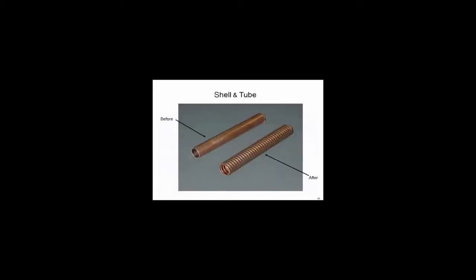Some changes: if you haven't looked at heat exchangers lately, whether they're chillers, evaporators, or single pass counter flow like we're talking about, the old designs were just standard copper tubing. The new designs are enhanced tubes. It's just spiral tubes, very simple, but what you're doing, you're creating some turbulence in there. You get a little more surface area out of it, and you're creating some turbulence to break up the inside film coefficients. You're breaking up the inside film coefficients, which in essence increases U, which means you can get away with more BTUs, the smaller surface area.